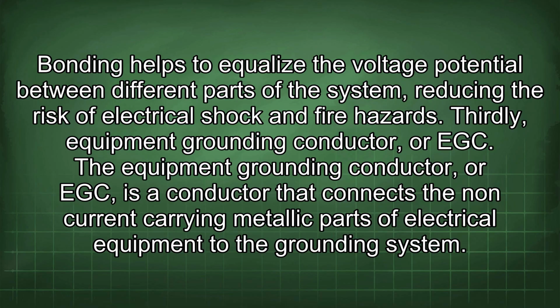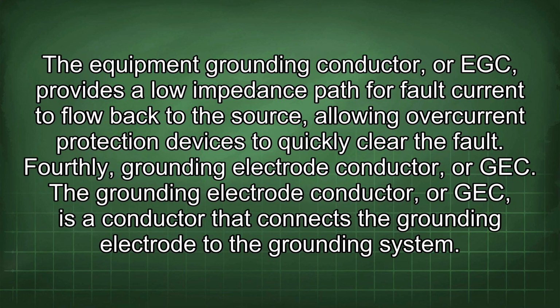Thirdly, equipment grounding conductor, or EGC. The equipment grounding conductor, or EGC, is a conductor that connects the non-current carrying metallic parts of electrical equipment to the grounding system. The equipment grounding conductor, or EGC, provides a low impedance path for fault current to flow back to the source, allowing overcurrent protection devices to quickly clear the fault.